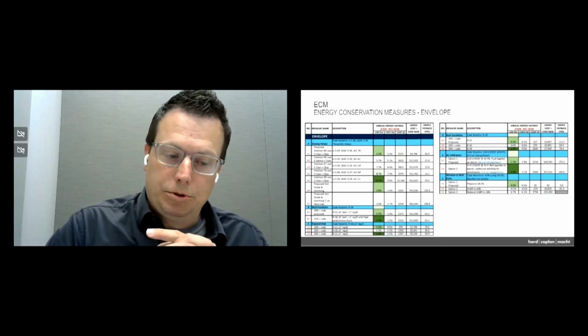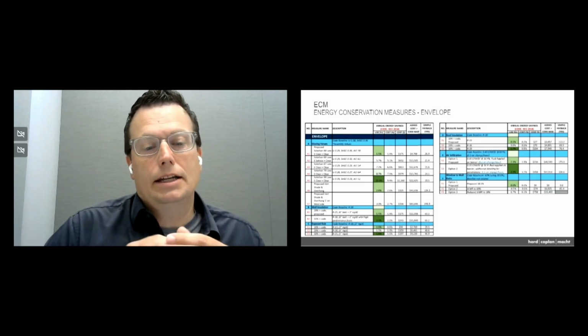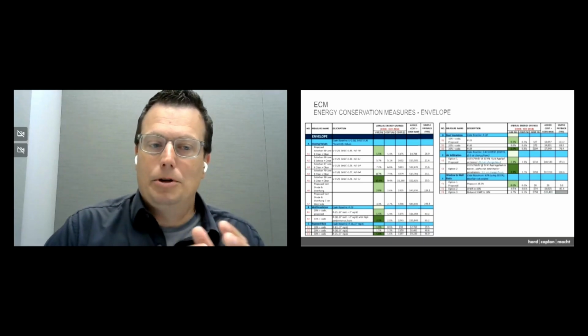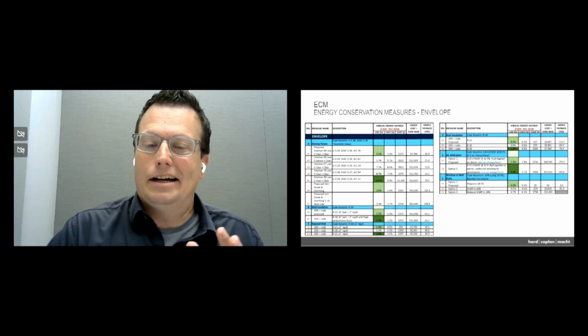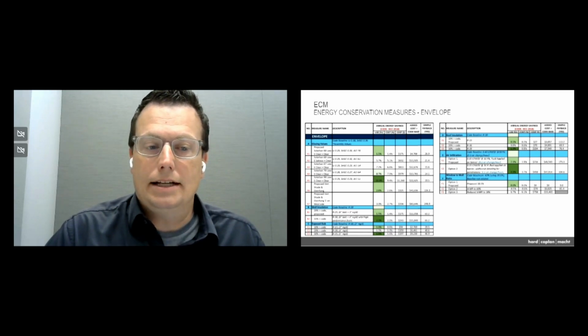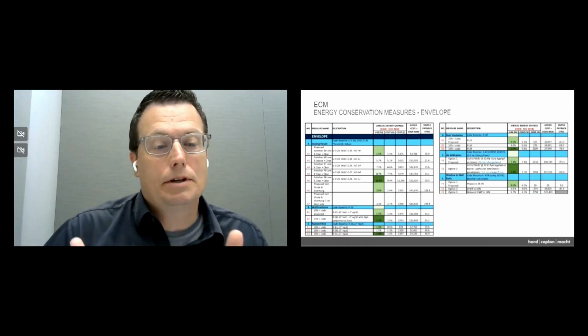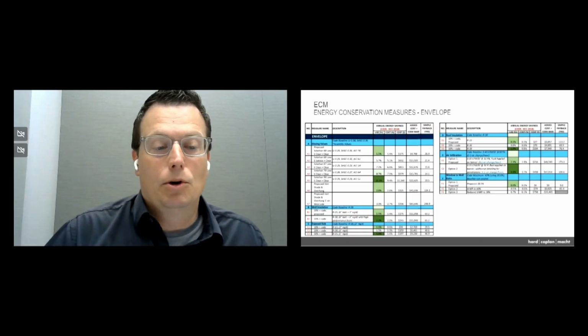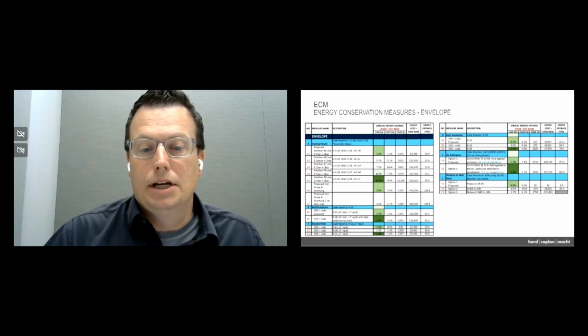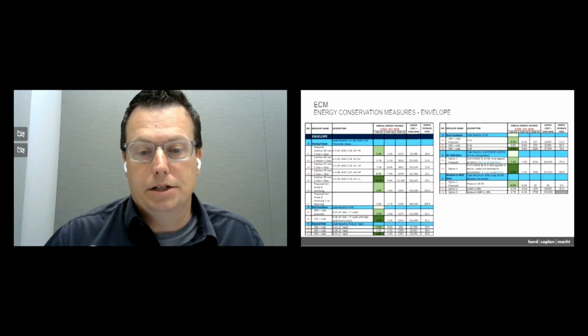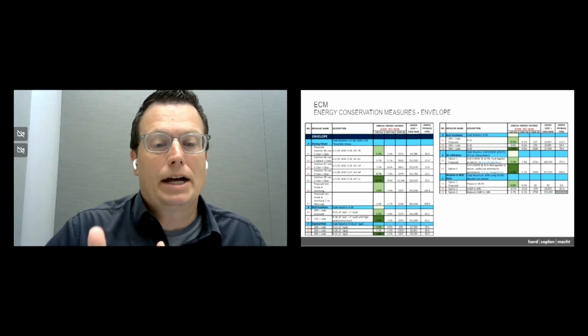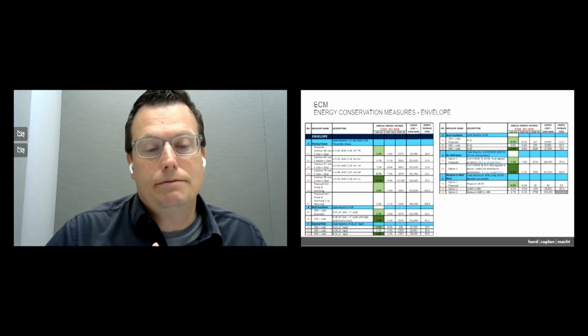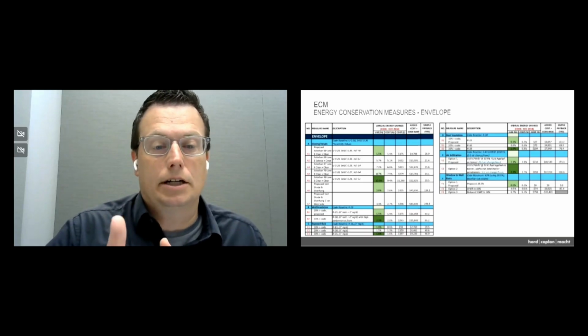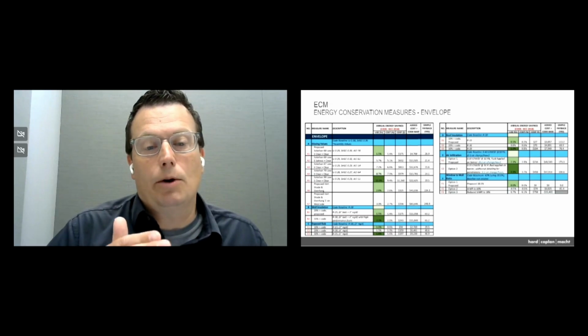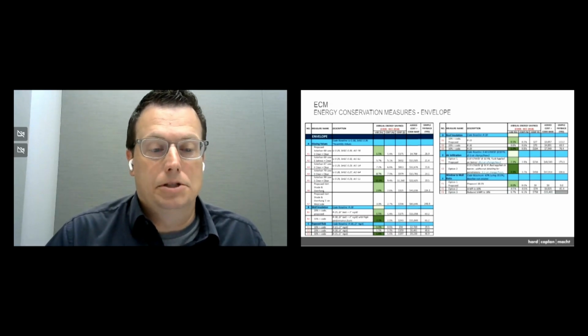To run through this with the client in an abbreviated version here today, we created a fancy spreadsheet that I'll try not to bore you with too much, but will hit the key ideas. Specifically for the envelope, we looked at glazing value, wall insulation, roof insulation, and window to wall ratio, testing different systems and amounts of insulation. We figured out how much energy savings we'd get, what that would pay back annually, and what the added first cost of those elements were.